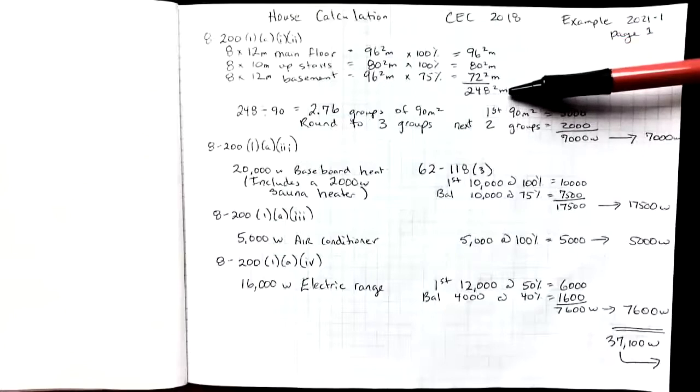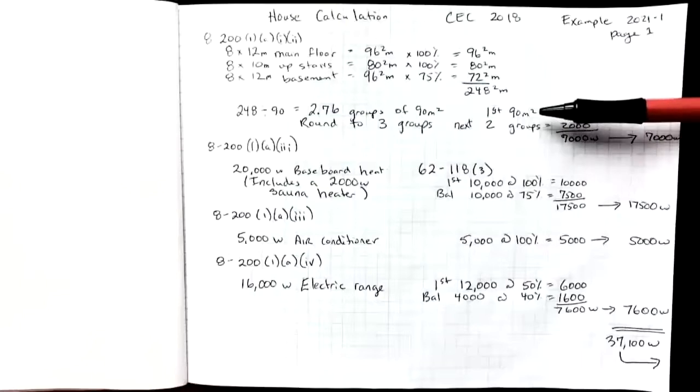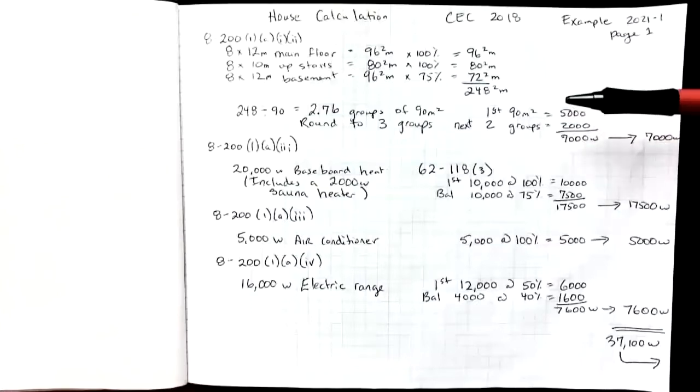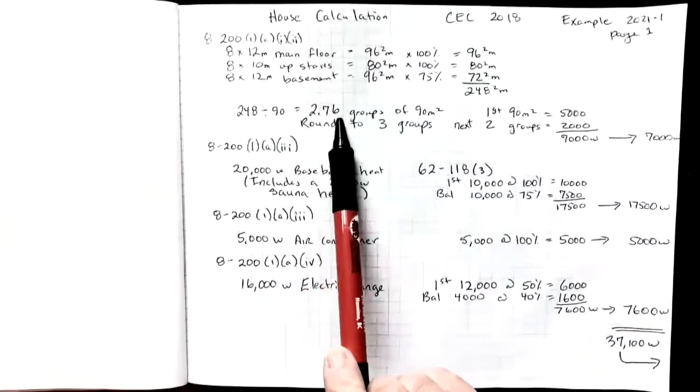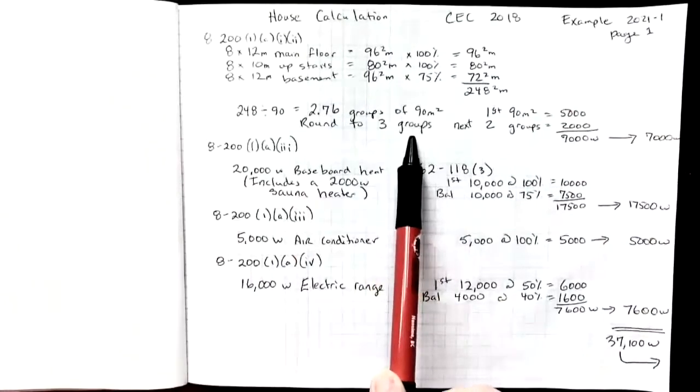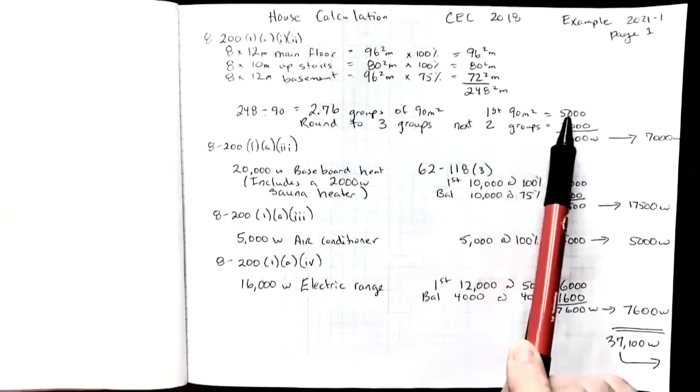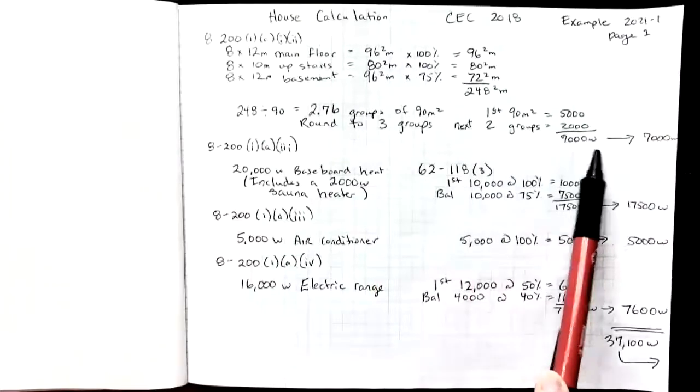This gave me 248 square meters and what I'm doing is I'm going to break that into groups of 90 meters squared because the code tells us to use for the first 90 meters squared we're going to have a demand factor of 5,000 and then for each group of 90 meters squared after that we're going to add 1,000 per group. So 248 square meters divided by 90 gives me 2.76 groups. Round that up to three groups because it doesn't matter if it's a part of a group or a whole group it still gets the full 1,000. So 5,000 for the first 90 meters squared, an additional 2,000 for the next two groups. My basic load would come to 7,000 watts.